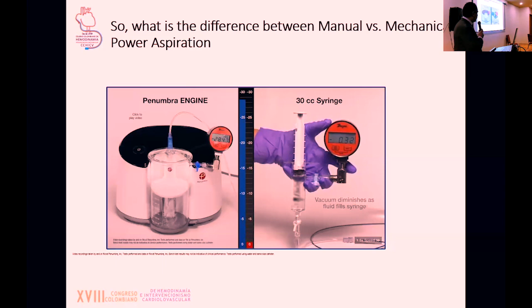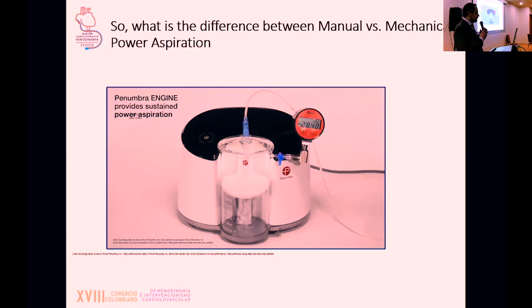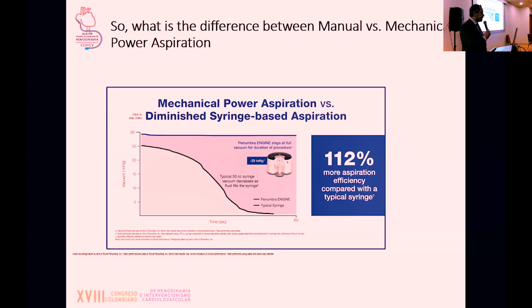So if you lose it in the coronary artery, no harm, no foul, because you have not caused any issue. But if you lose it outside the guide, it can dislodge and go to the brain and cause a stroke. With continuous aspiration, you see continuous suction of almost negative 28 or 29, and that does not change by how fast or how slow you're proceeding. We see this in the graph, and you see a very stable continuous suction in the continuous mechanical thrombectomy, whereas in manual thrombectomy you lose that.